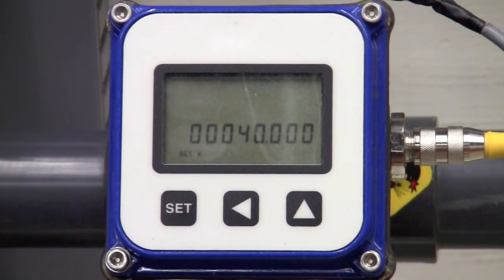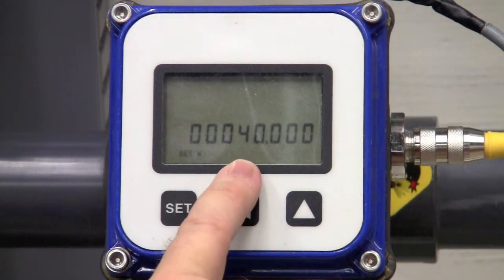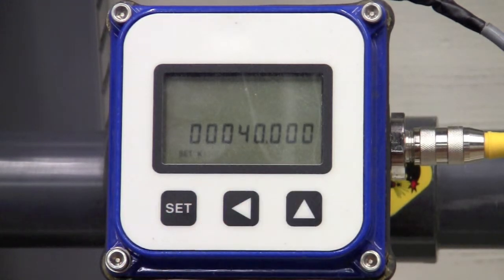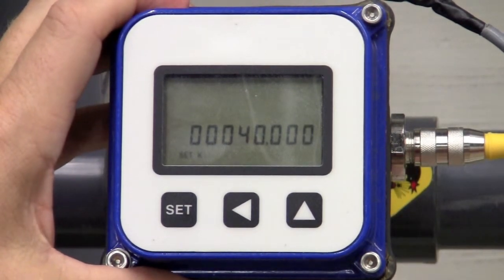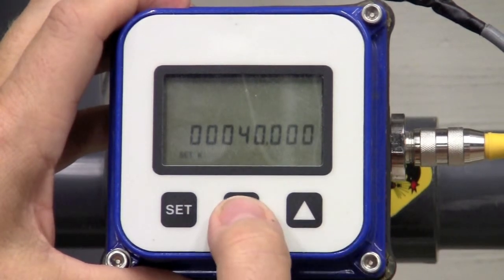Your first configuration parameter is your k-factor. Currently, I have 40.000 as the k-factor. The k-factor is the number of pulses per gallon. So, let's say I wanted to change that k-factor.